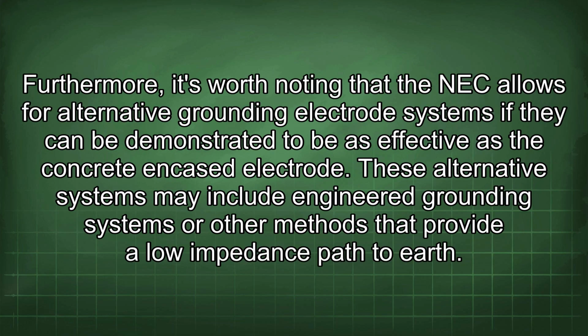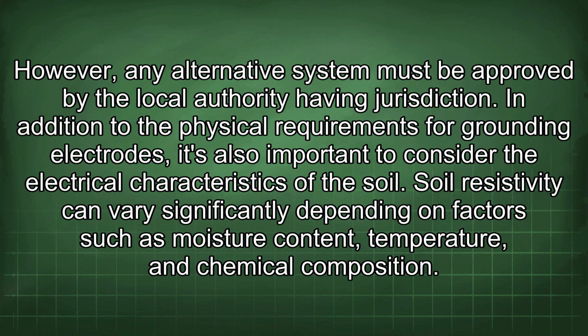Furthermore, it's worth noting that the NEC allows for alternative grounding electrode systems if they can be demonstrated to be as effective as the concrete encased electrode. These alternative systems may include engineered grounding systems or other methods that provide a low impedance path to earth. However, any alternative system must be approved by the local authority having jurisdiction.